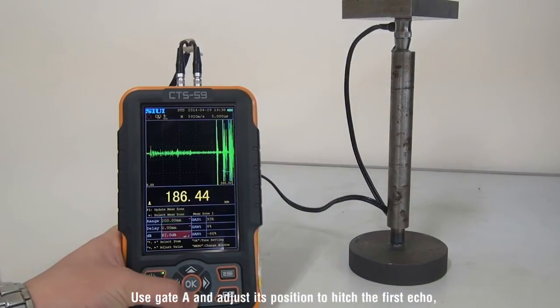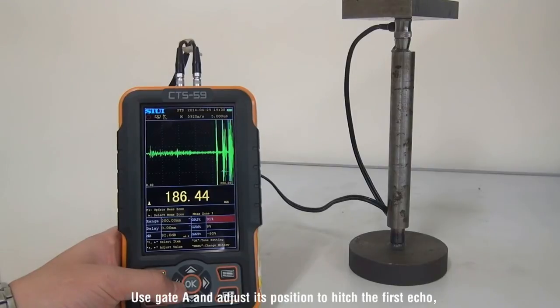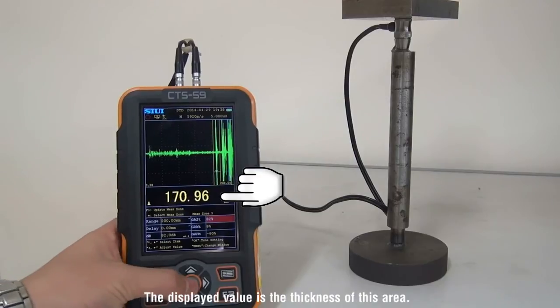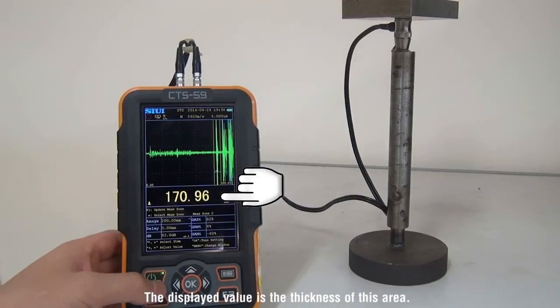Use Gate A and adjust its position to hit the first echo. Click F1 key to refresh the value of this area. The displayed value is the thickness of this area.